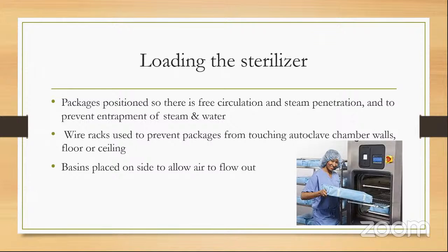And in the picture that's inserted there, you can see the surgical tray that is wrapped, the indicator tape on the outside, and on the inside there would be indicators and a surgical sterility indicator as well. Note the wire racks that prevent the packages from touching the floor, the sides, or the ceiling of the autoclave.